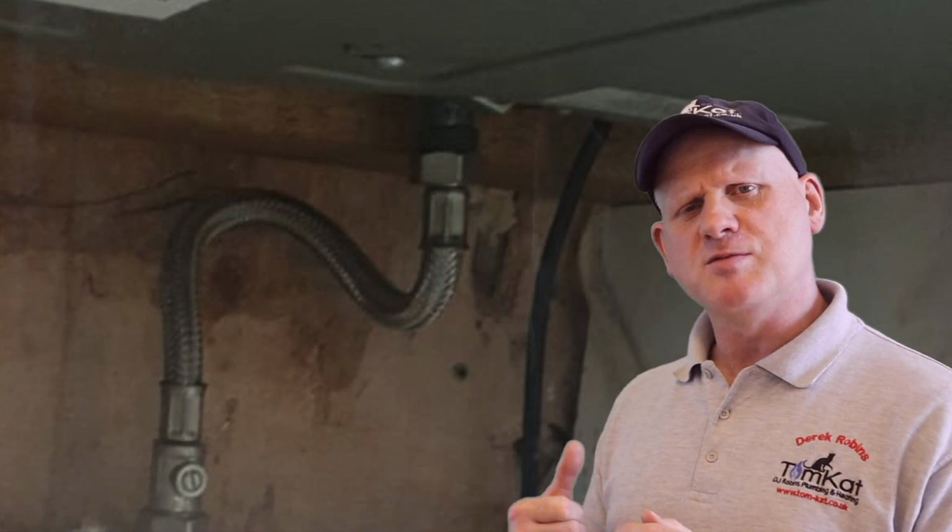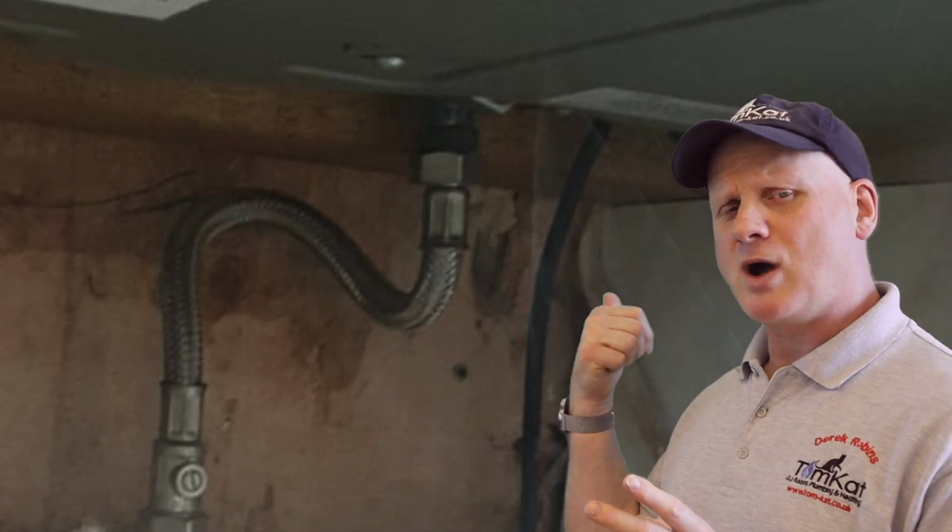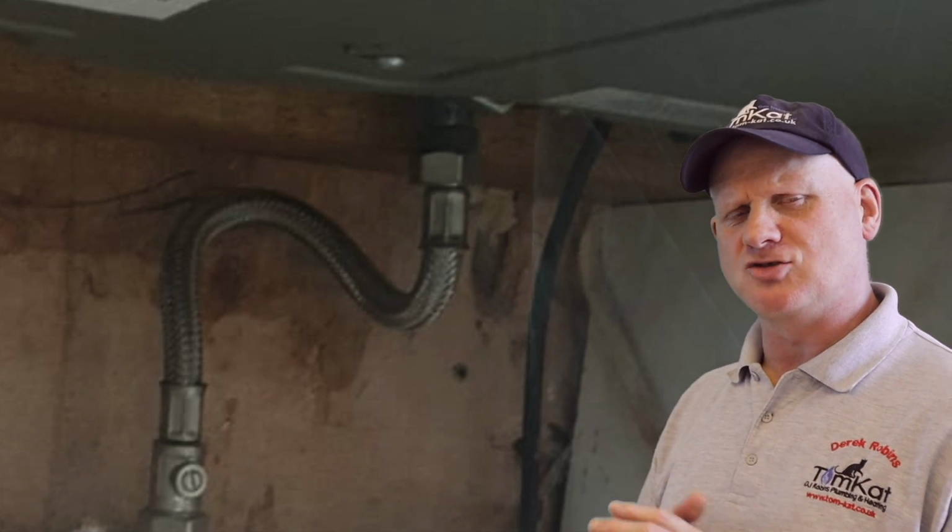You're there to do a landlord's report, you remove the oven. Now some engineers say you can't remove the oven. My personal opinion on it is, if you don't remove the oven, then you're not going to find something like this. Also, they've told you the landlord installed it, not a gas engineer. So how are you going to categorise this situation, and what are you going to do?